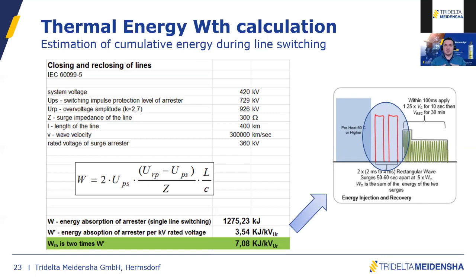As a manufacturer, we cannot tell you which energy needs to be absorbed by the surge arresters considering your system parameters. We can only tell you that we have done the test on our block and we can give you the confidence that this block will withstand this energy. And one of the changes in the IEC was to harmonize the simulated or calculated value with the test which is done by the manufacturers.